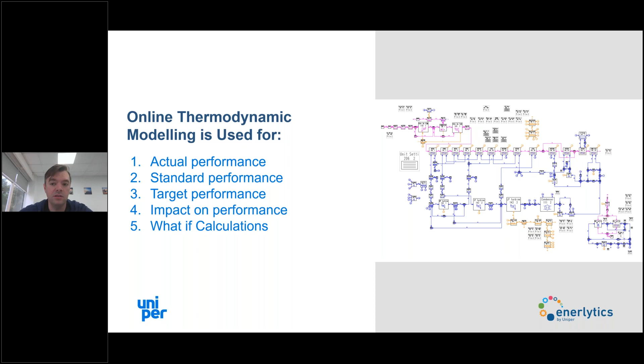Additionally, we can then see for each of these individual parts of the plant what is the impact of each of those components on its performance, which then enables us to do what-if calculations. So what if I replace the condenser or clean the condenser, what would the impact be? What if I added a cooling tower or removed a cooling tower from operation? What would be the improvement?